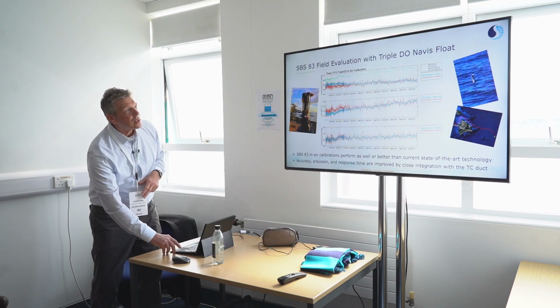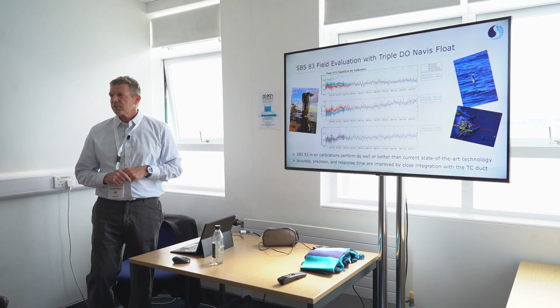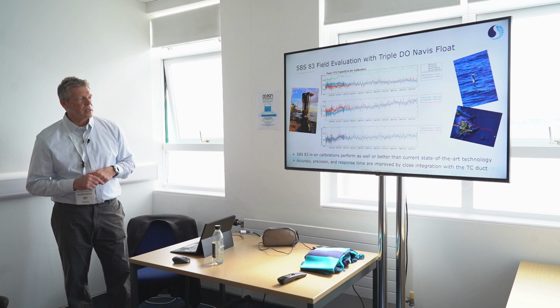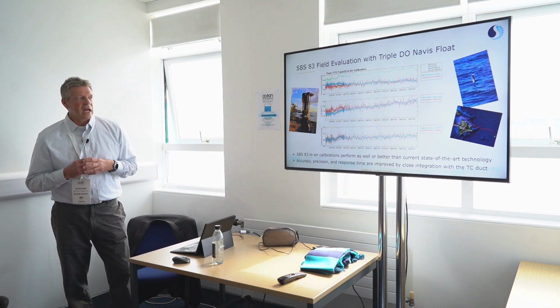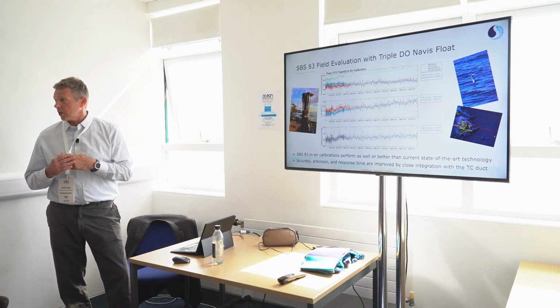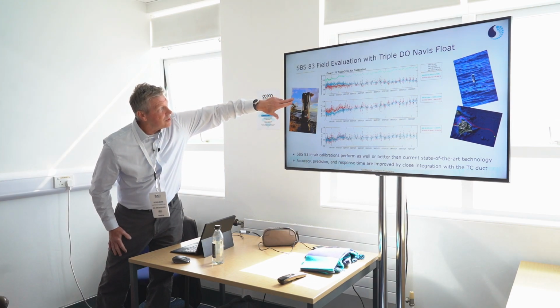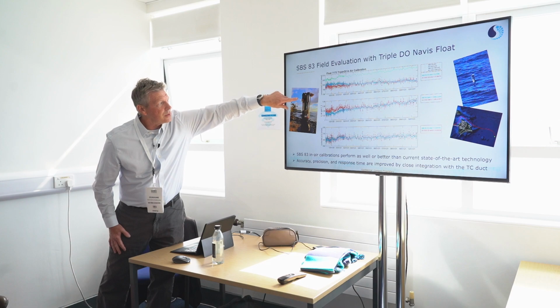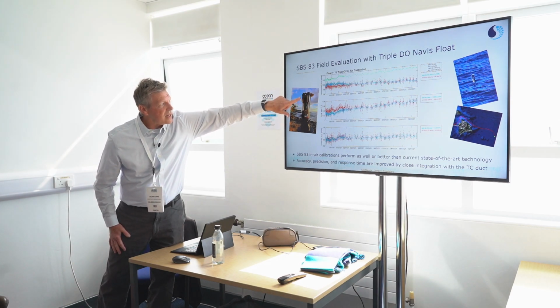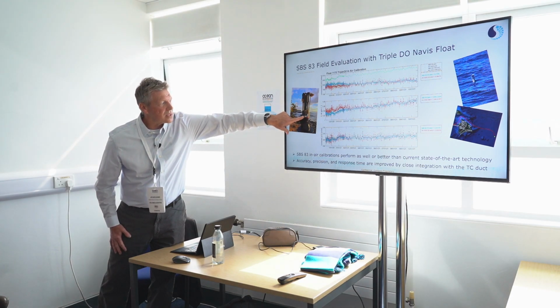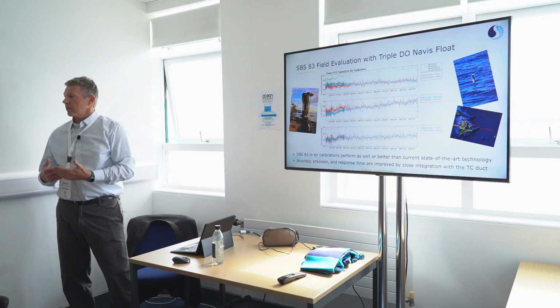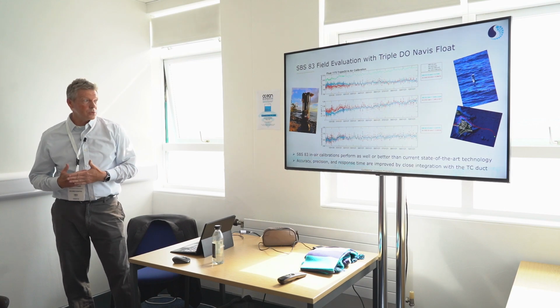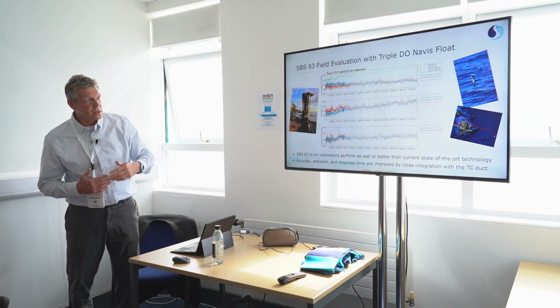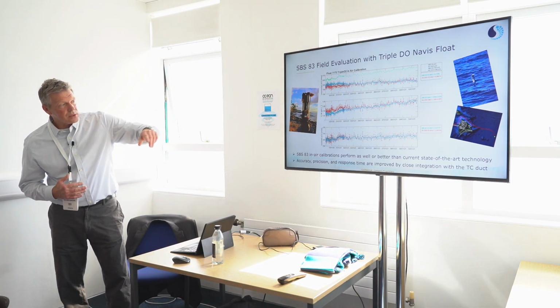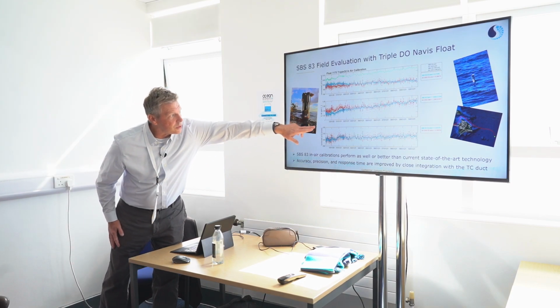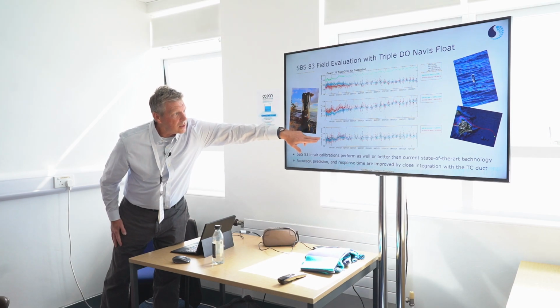And as I said before, a lot of the difficulty is in really validating whether it actually works. So the way we approach that is we manufactured a specific Navis float that included 3 optical oxygen sensors. We had an Aanderaa 4330 in here. I think it's really hard to see. We had the new prototype of what we call the SBE 83 sensor. And then we had the original SBE 63 sensor still in the float. And that really helps us to do intercomparison between the sensors and evaluate their performance with regard to each other. So even in the alpha deployment that you can see here, which was done off Hawaii on one of the Navis floats, you can see a pretty good agreement in the data after you correct it with the in-air gain between the two sensors.